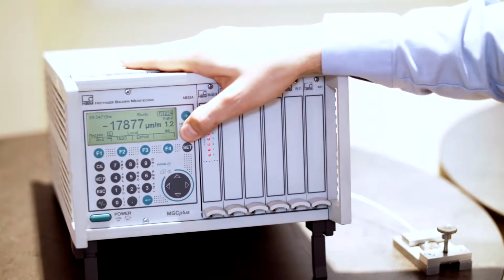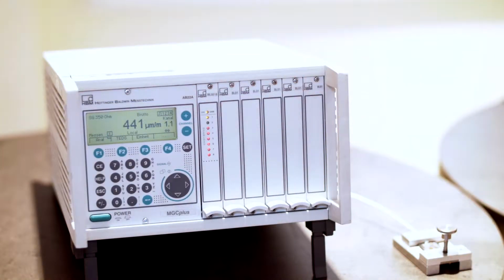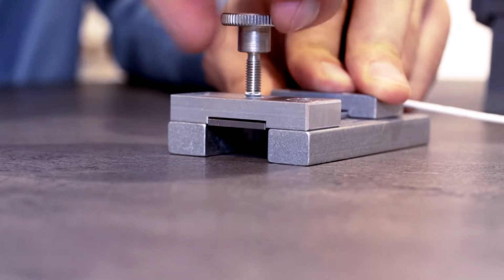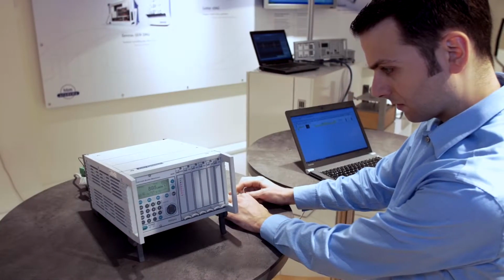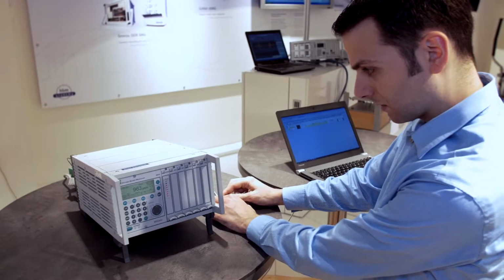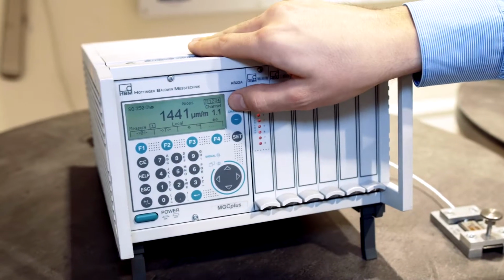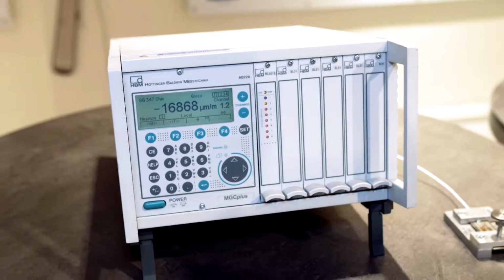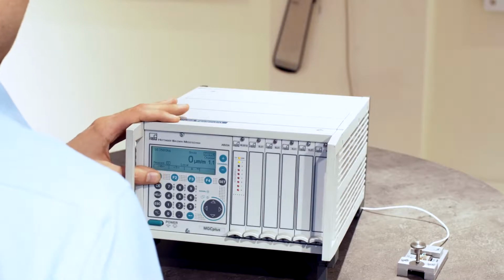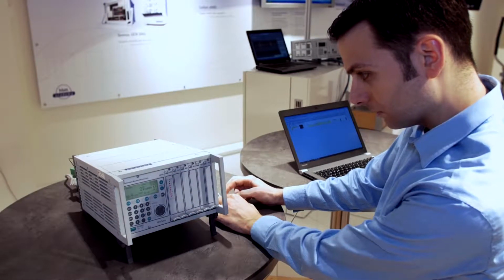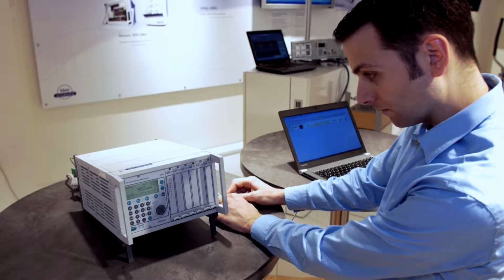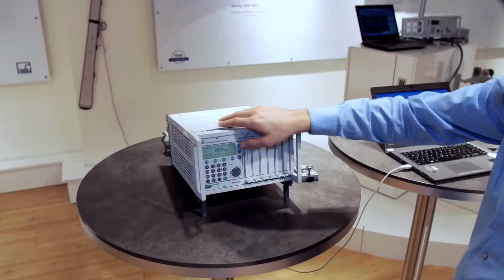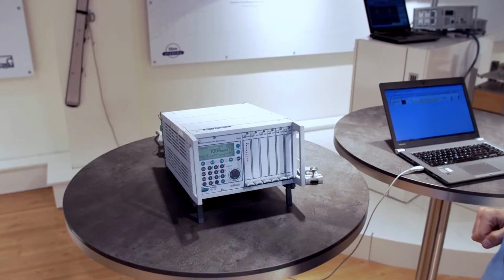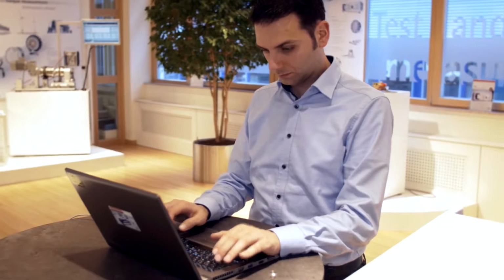At first, the initial values of both strain gauges are recorded, and a mechanical strain of approximately 1,000 micrometers per meter is applied to the bending beam. As expected, the measurement system measures this strain in a uniform way. The next step is to set the initial values to 0. When once again applying a strain of approximately 1,000 micrometers per meter, both channels display almost the same measured value. The mutual compensation of nonlinearities, therefore, gives excellent results in both cases.